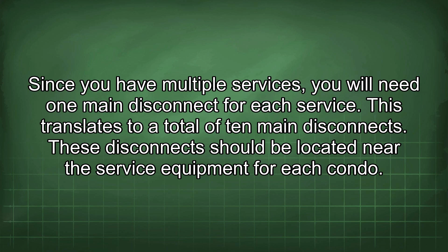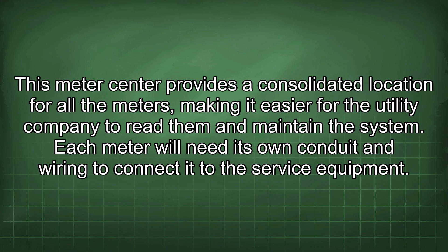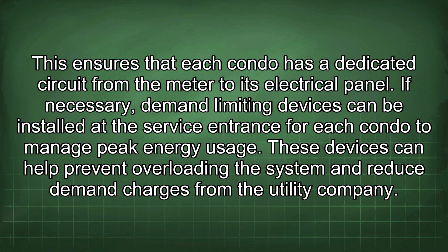This meter center provides a consolidated location for all the meters, making it easier for the utility company to read them and maintain the system. Each meter will need its own conduit and wiring to connect it to the service equipment. This ensures that each condo has a dedicated circuit from the meter to its electrical panel. If necessary, demand-limiting devices can be installed at the service entrance for each condo to manage peak energy usage. These devices can help prevent overloading the system and reduce demand charges from the utility company.